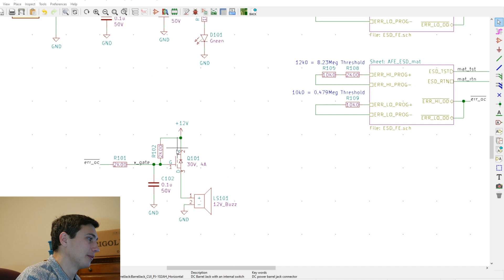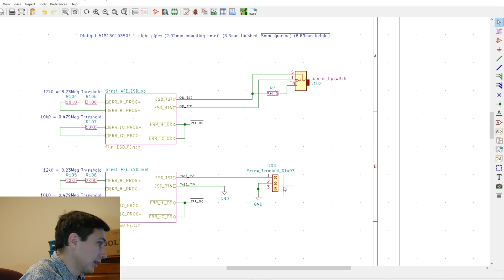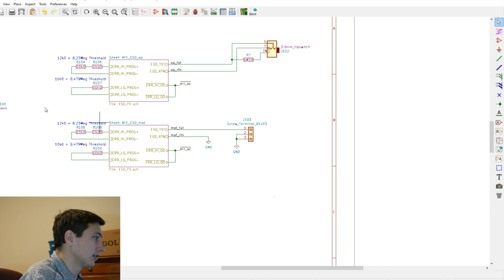Alright, let's walk through the outputs here. For the mat, here's what we need: a place for the ground conductor to attach to this board, the actual earth ground. Since the 12 volt input is isolated, we need to tie this back to ground, so there's one terminal of this terminal block for that connection, and then there's a spare, because you've got two options.